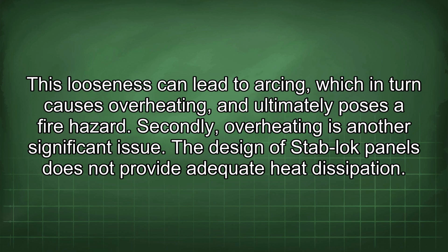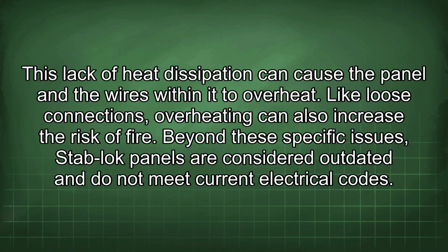Secondly, overheating is another significant issue. The design of Stab-lok panels does not provide adequate heat dissipation. This lack of heat dissipation can cause the panel and the wires within it to overheat. Like loose connections, overheating can also increase the risk of fire.